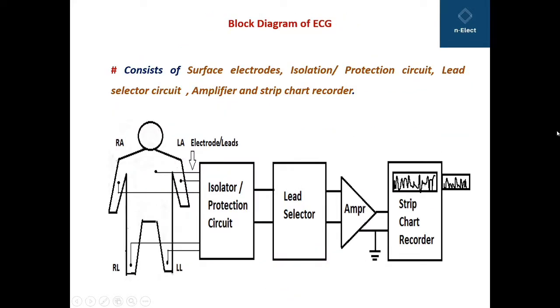For the block diagram of ECG, you can clearly see here the connections which are directly provided to the body of the patient. These are the leads and electrodes, and thereafter comes the isolator or protection circuit. Then the next block is the lead selector, then the bioamplifier, and the last block is the strip chart recorder, or the display unit.